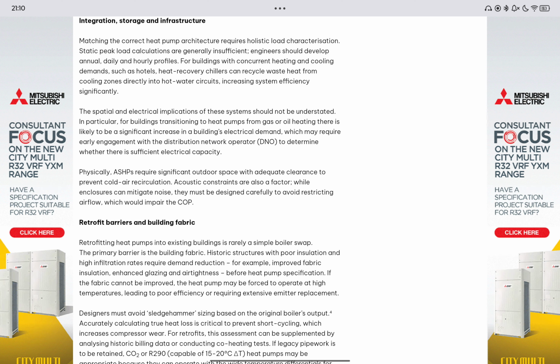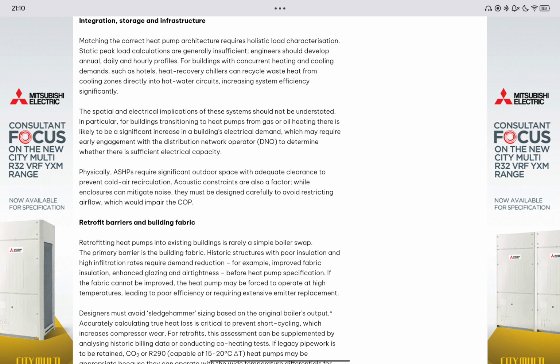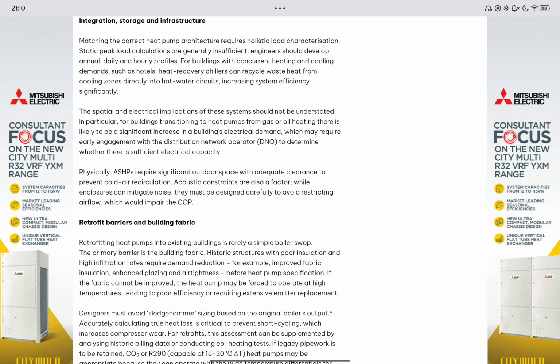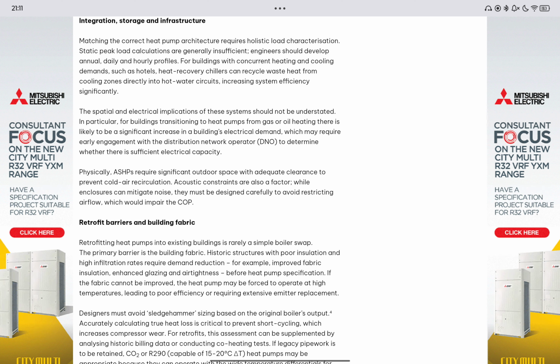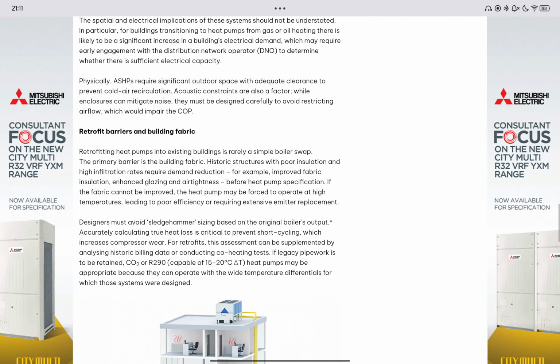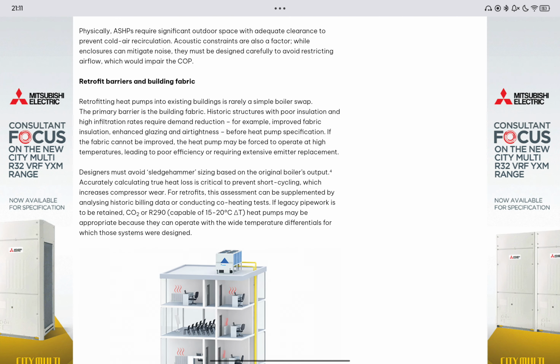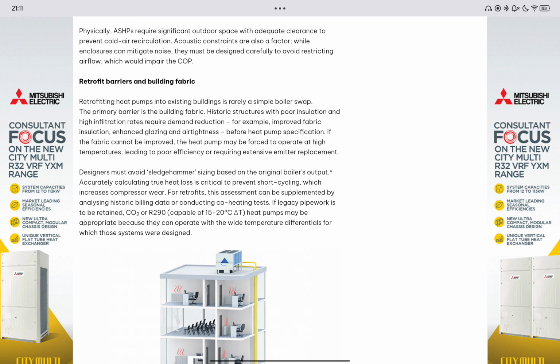Physically, air source heat pumps require significant outdoor space with adequate clearance to prevent cold air recirculation. Acoustic constraints are also a factor. While enclosures can mitigate noise, they must be designed carefully to avoid restricting airflow, which would impair the COP, or coefficient of performance. Retrofit barriers and building fabric.